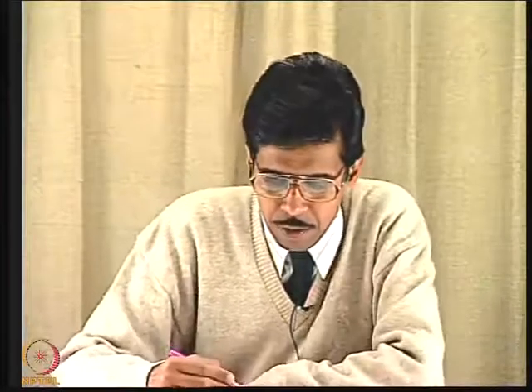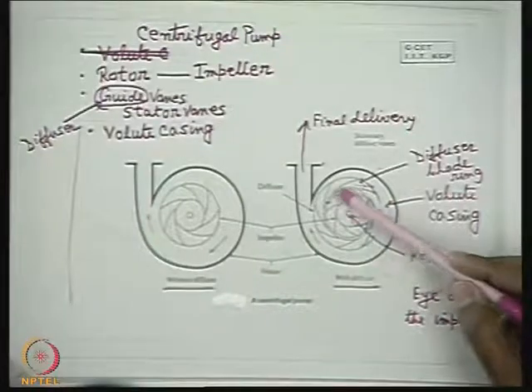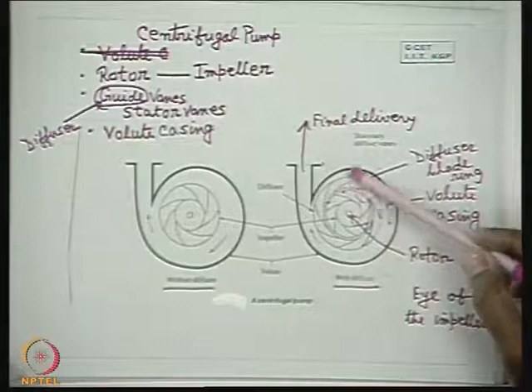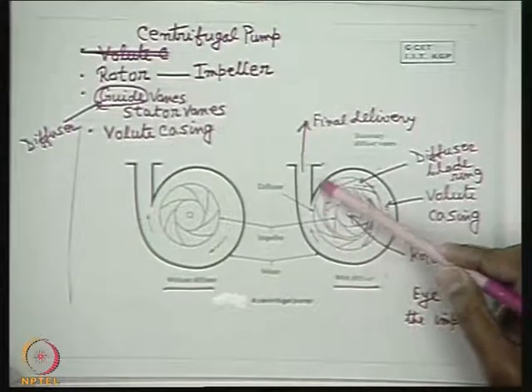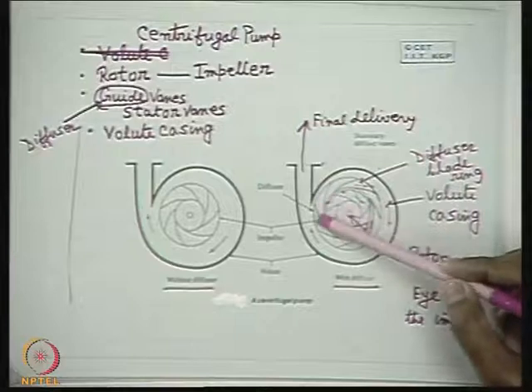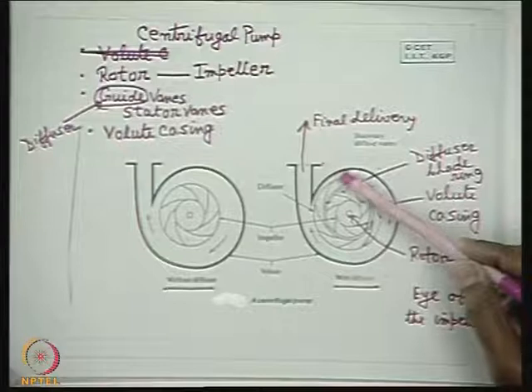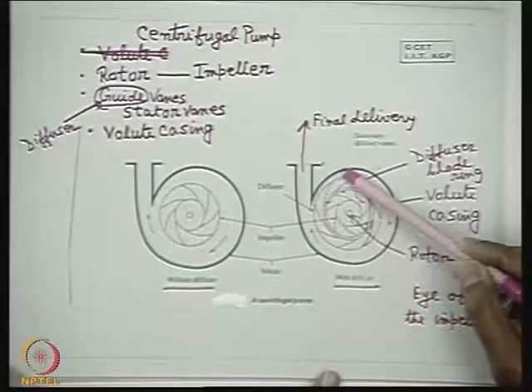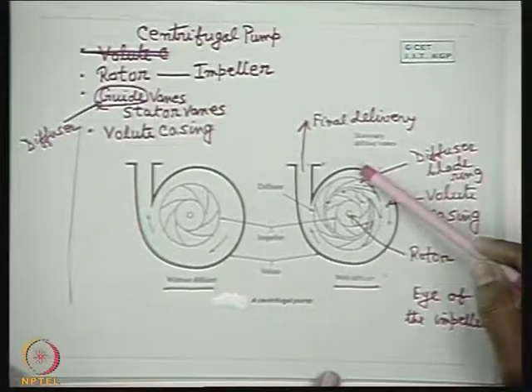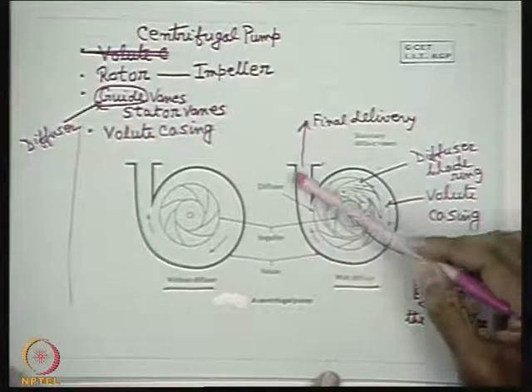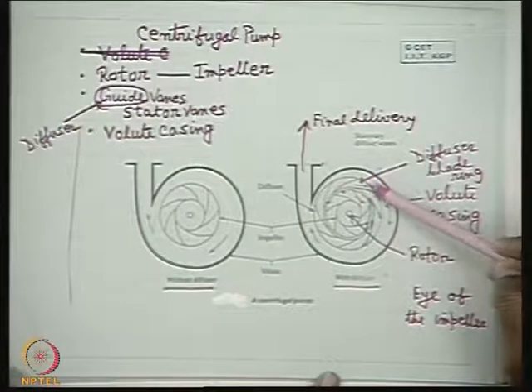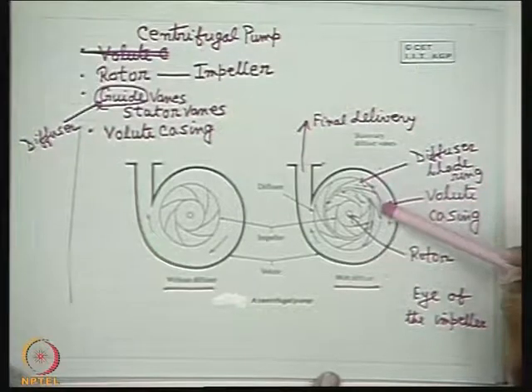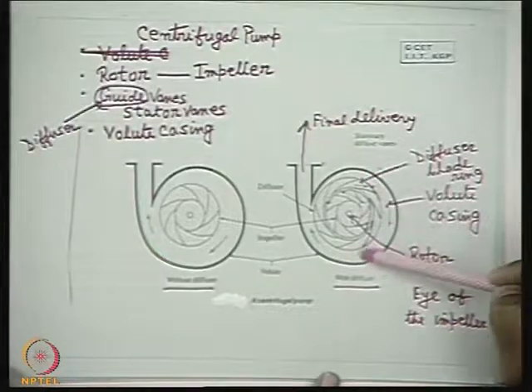Looking at the different components of a pump, we see the pump impeller. After the impeller there are two types of diffusers. One is the vane diffuser, where a number of static vanes form a diverging passage — as the fluid flows through this passage, its pressure is increased while velocity is decreased. After the vane diffuser, the fluid enters the volute casing or spiral casing, where the cross-sectional area increases in the direction of flow, causing an additional conversion from kinetic energy to pressure energy.